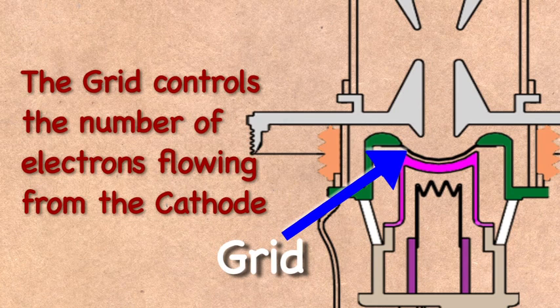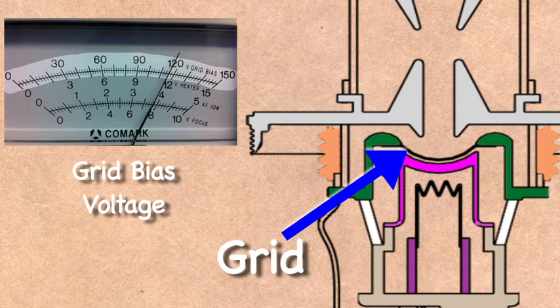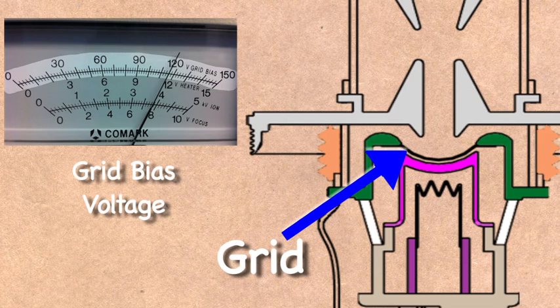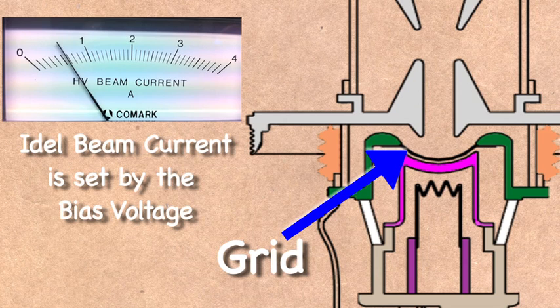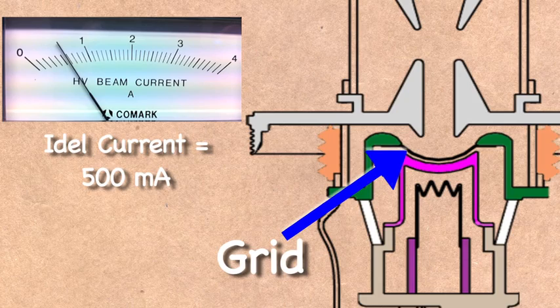To control the beam of electrons traveling from the cathode to the collector, the grid is biased to limit the amount of electrons. The amount of current flowing through the IoT with no RF applied is called the idle current, and that sets the gain of the tube also.